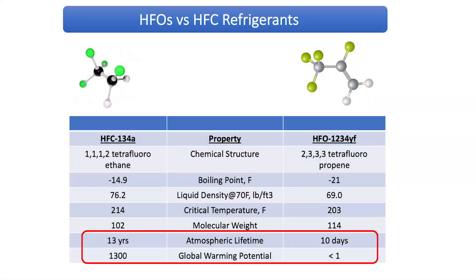The basic properties of an HFO can be compared to an HFC if we put them up on the screen here. A very common molecule, R134A, is an HFC. Something very similar, R1234YF, is an HFO. If you look at the structures and the atoms, they all look pretty similar with the exception of that olefinic bond. But what that olefinic bond does really shows up when you look at the atmospheric lifetime — the short atmospheric lifetime of the HFO versus the longer one for the HFC. Things like boiling point and densities, those other properties that are important in refrigerants, remain the same.